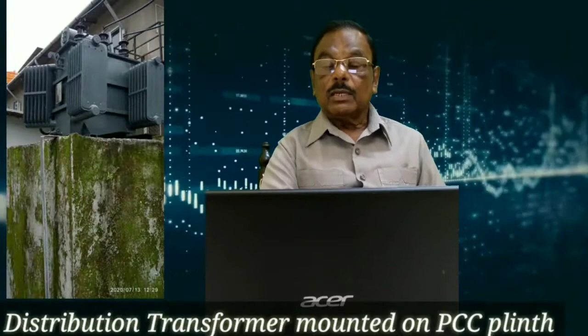It not only records your power consumption but also other parameters such as power factor, etc. Nowadays, even smart tri-vector meters are installed, whereby the electricity department need not come to your site for taking the readings but can measure it remotely from their substation and issue you the bills. The second section of the substation belongs to the consumer. It also consists of a 2-pole structure with necessary insulators, lightning arresters, HT fuses, GOAB switch, and then the distribution transformer, usually mounted on a PCC plinth.